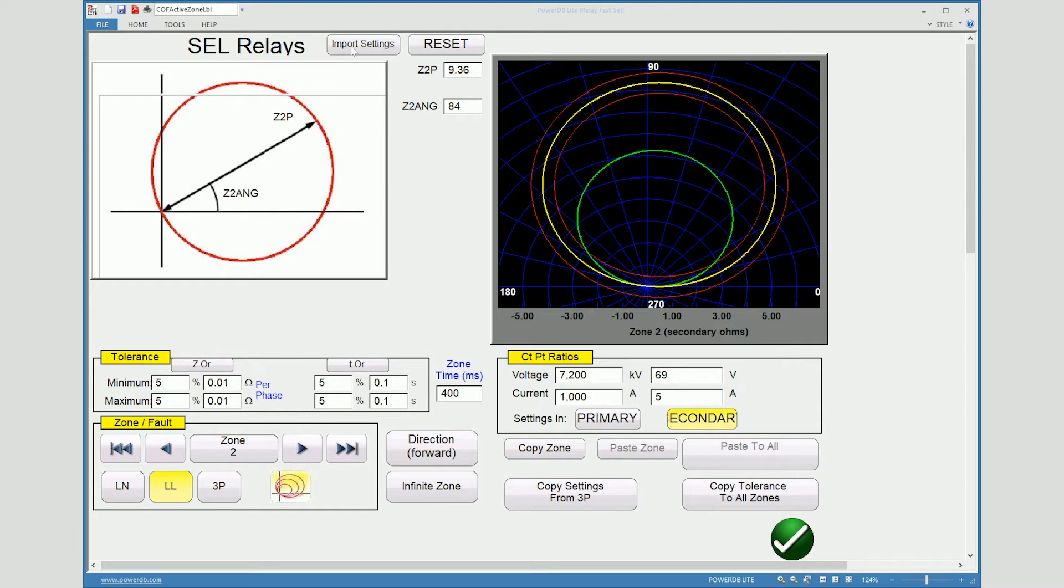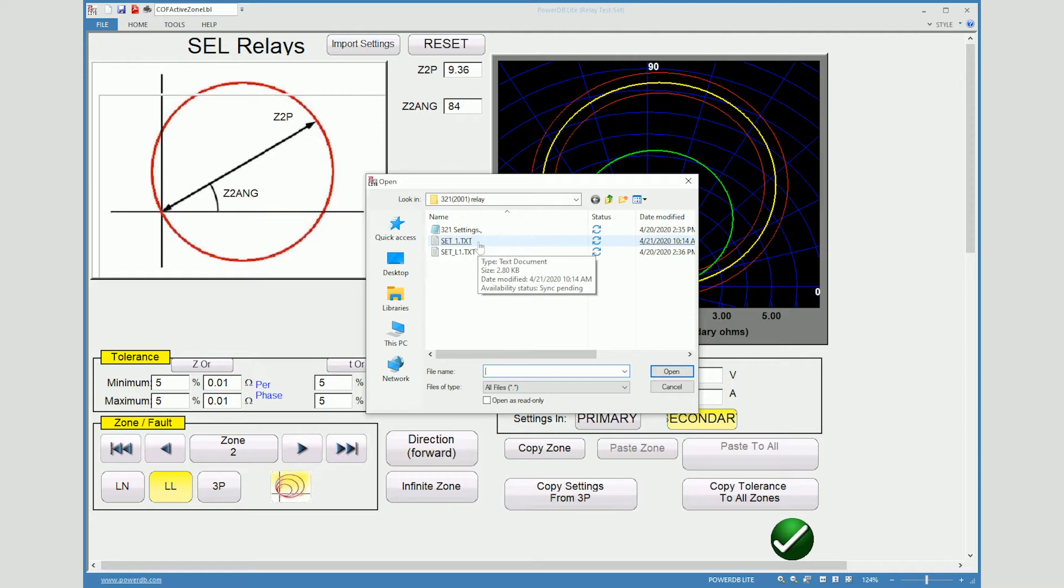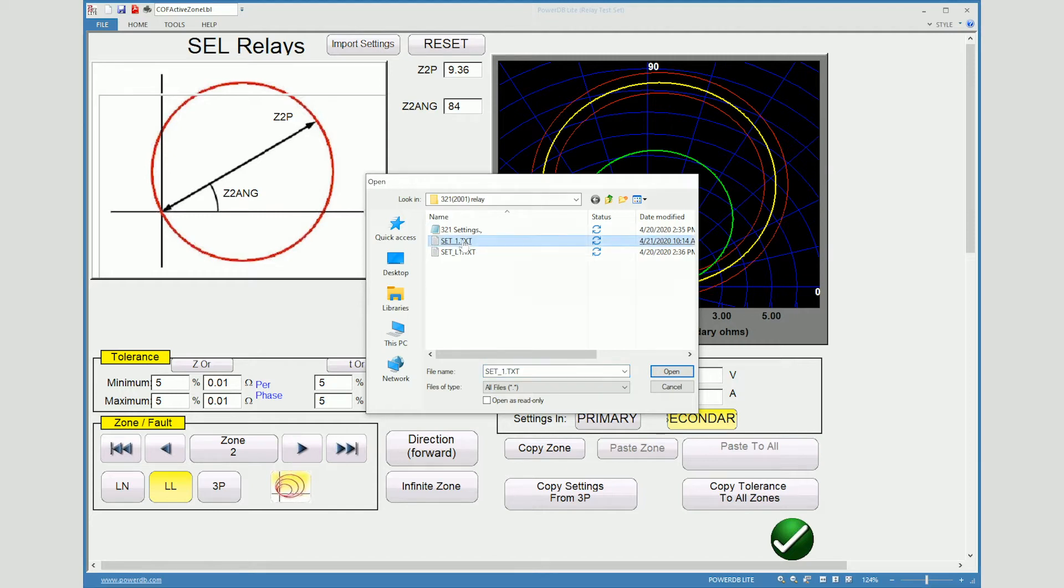So what we would need to do here is actually input settings that are from the SEL template. So we can come up here to import settings. We can come down to the setting file that I had created using the SEL software to get it into a text file. So we have to make sure that we export these to a text file .txt. So I'll select set.